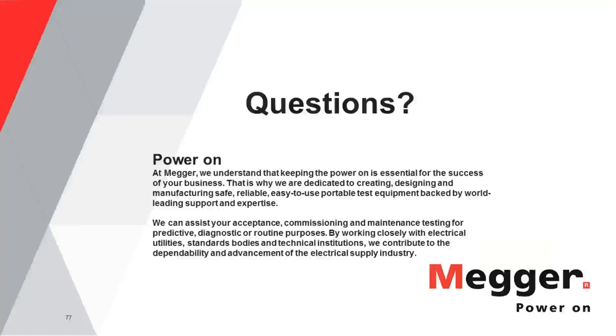Okay, thank you, Volney. Next question for Volney again. What does the SOP acronym mean? Well, I guess it's step overpotential, which is one of the tests that Jeff mentioned, and also a useful test to determine if an insulation is in good condition. This is a test in which you increase the voltage every minute and you do 5 steps, and you are expecting to get a constant value of resistance.